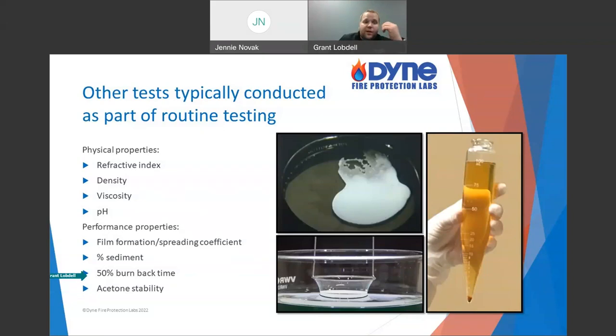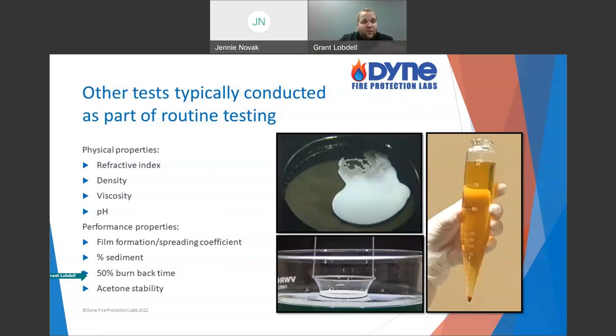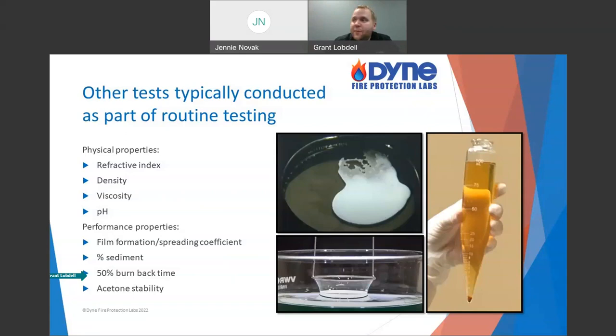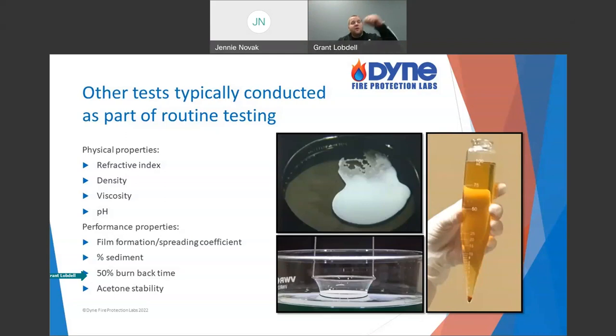The burn back test is more involved — we use IPA, another polar solvent. We apply the foam blanket, then actually start a fire in the middle, expose the foam to the fire, and see if it'll put it back out. This is a small-scale version of what's done at UL 162, where for full listing you do almost a 50 square foot fire test: extinguish the fire, then put a stovepipe in the middle, scoop out some foam, re-ignite it, pull out the stovepipe, and see if the foam blanket can put it back out. That's a burnback test.